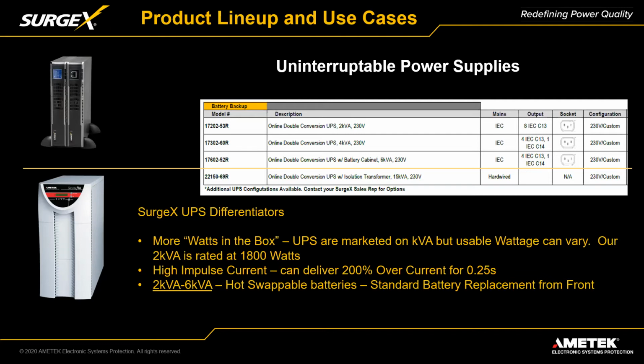On those rack mount units, the batteries are hot swappable, which is a big deal when you're talking about service. What's shown there, where the SurgeX logo is in the bottom section, that front panel pops off when it's rack mounted, and you pull the battery tray out and disconnect the battery. The output still is on, it's still doing its double conversion online UPS, so you don't have to turn the rack off.